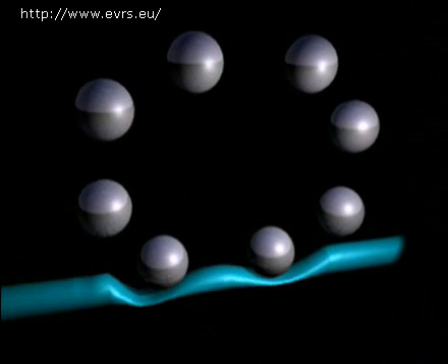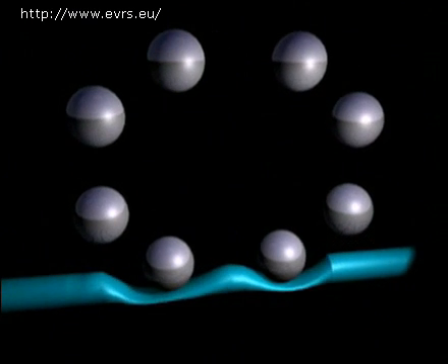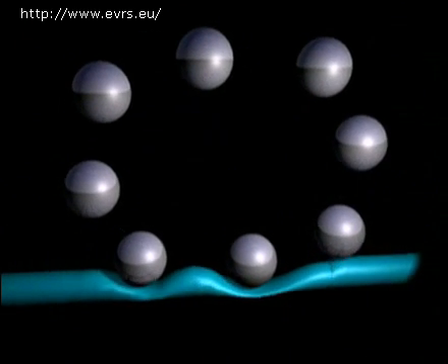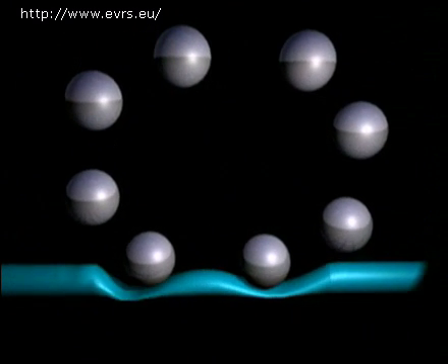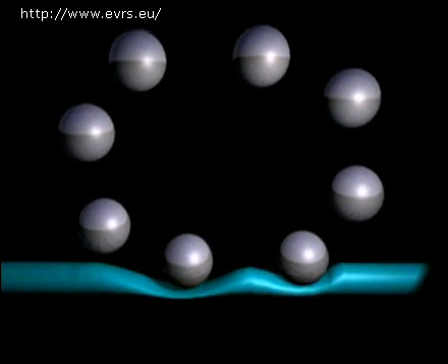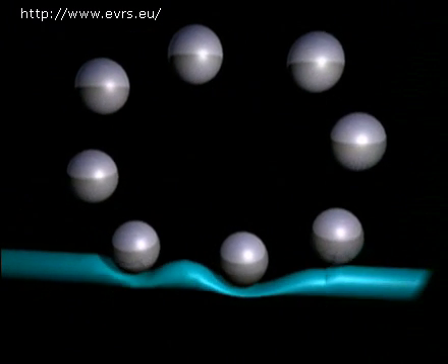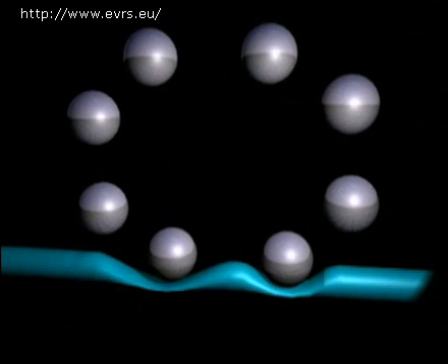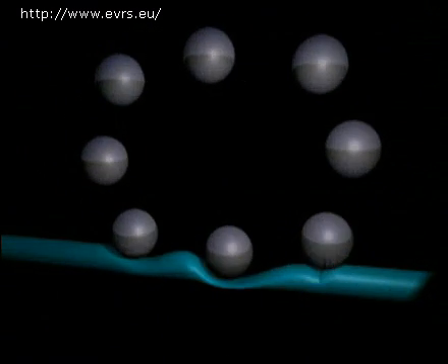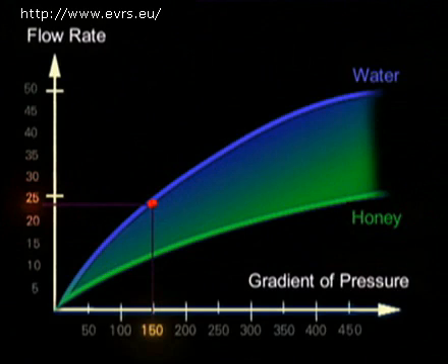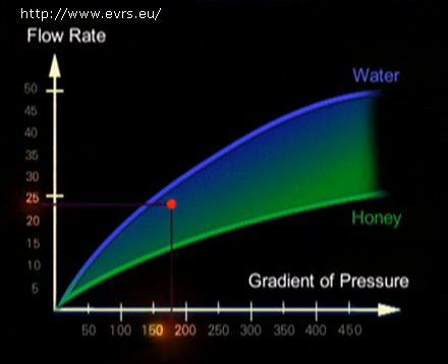With a debimetric pump, as with the peristaltic one, the column of aspirated fluid, which fills the space that was created by the rollers, is going to be the same no matter what the viscosity of the fluid is. The flow caused by the rotation of the rollers will thus be constant, but it will bring about varying depressions at the pump level according to the aspirated fluid's viscosity.